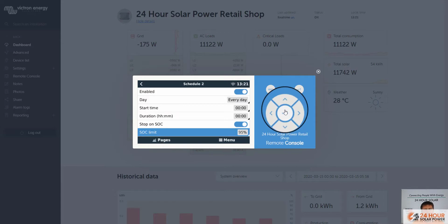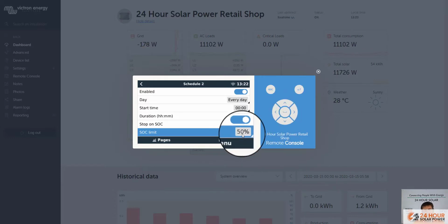Say, for example, if you want to take advantage of off-peak energy in the middle of the night, you can go in here and say, right, at midnight, I want to charge the batteries up to 45% or 50%. So they actually start charging and charge to 50%. We do this a lot when someone's living in an area that has really high peak energy rates in the morning. So we're taking energy that's, say, 20 cents at night, and we're going to charge the batteries up. Then only for maybe 2 hours in the morning are customers using their peak energy. So we use it in that situation so that we stop them ever buying from the grid in those first 2 hours, when it's jumped up to 40 cents, really doubled the price. And then it goes back to solar.